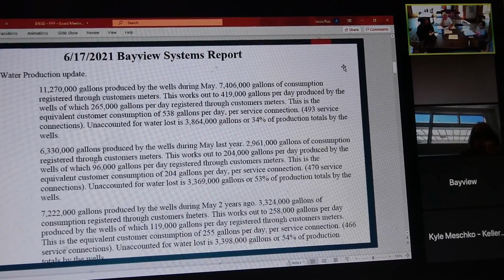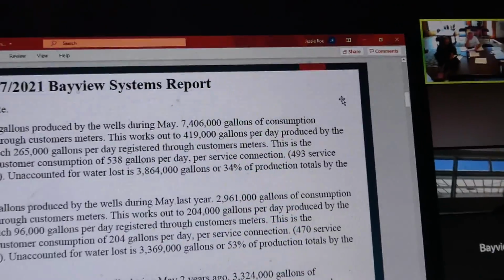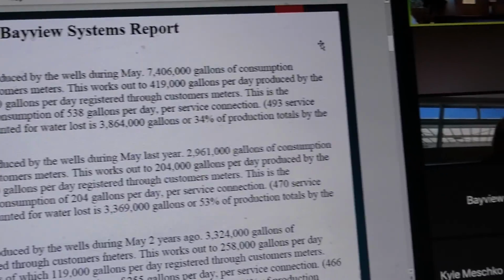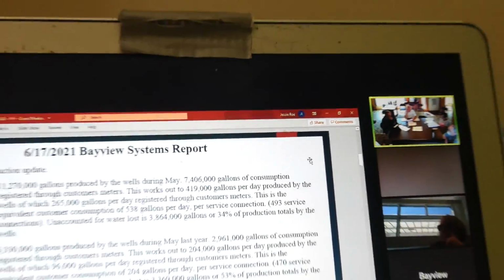Because Ian and I were reading the meter, we went back and said, is this possible? Did we make a mistake in our reading last month? That's why the lake fills up that high. Well, the next thing you look for is, if it's a 1-inch meter, 50 gallons a minute, it's not possible to put that much out. But a 3-inch turbo meter? Oh, it sure can. Those put out a lot more water.